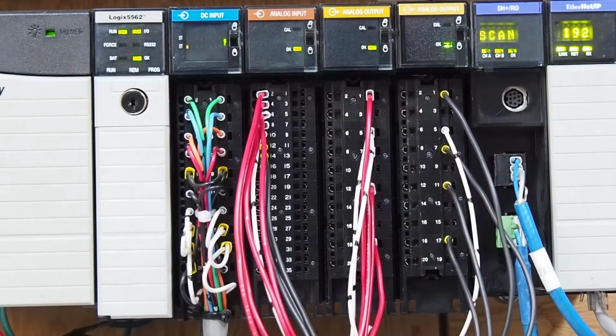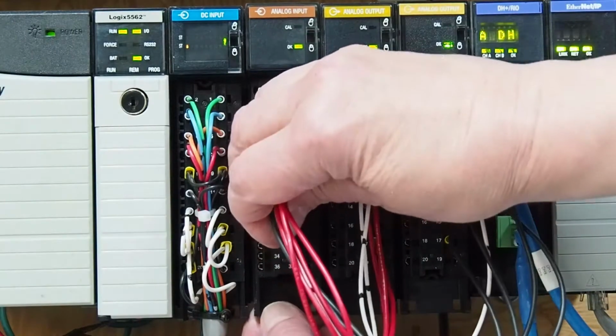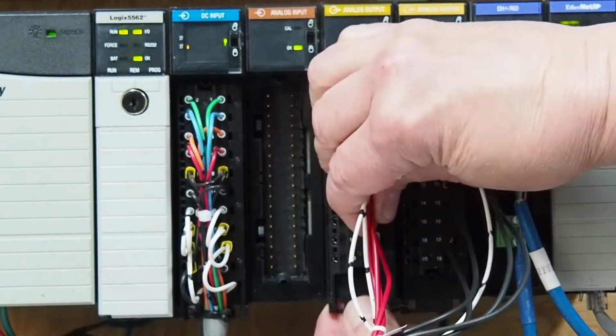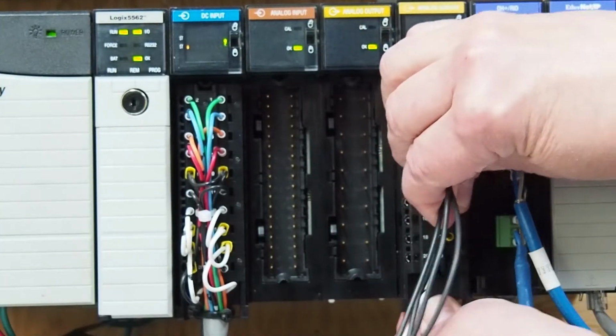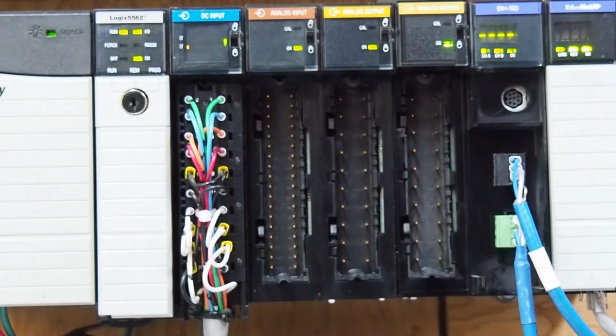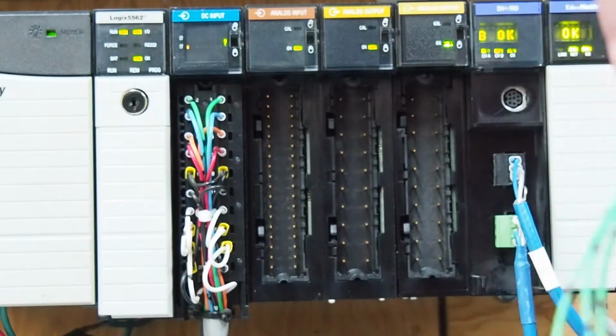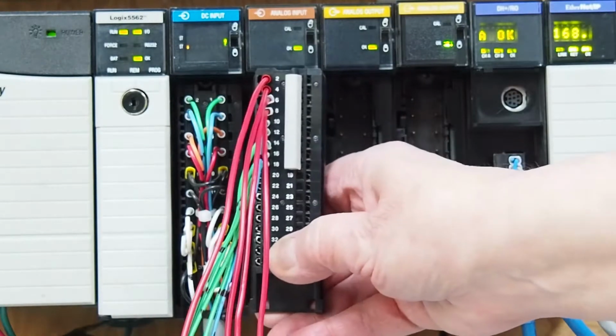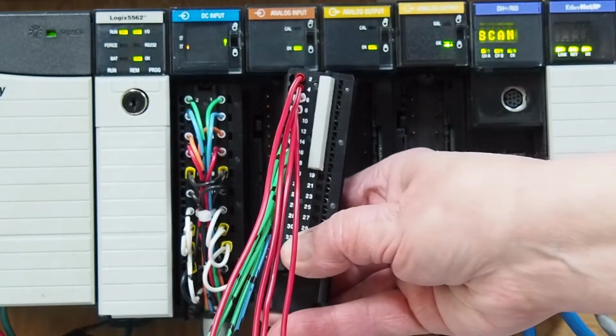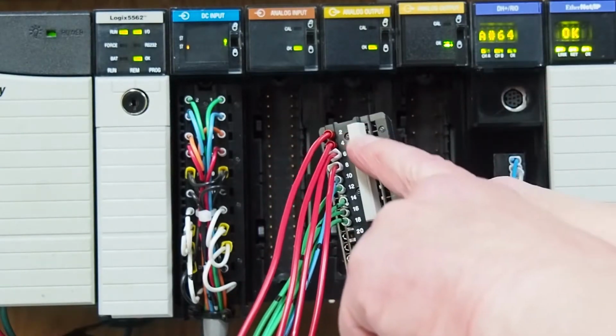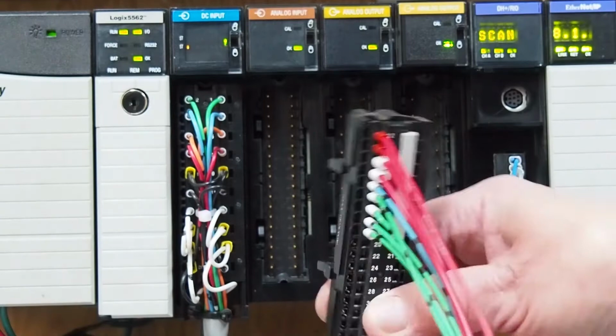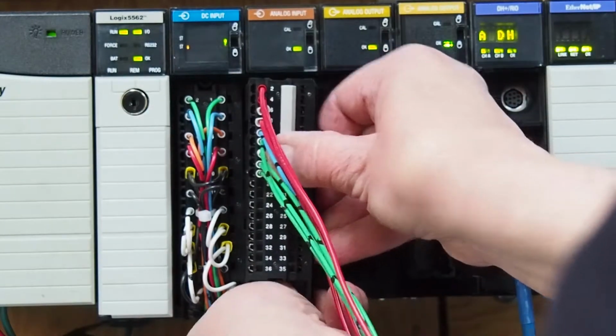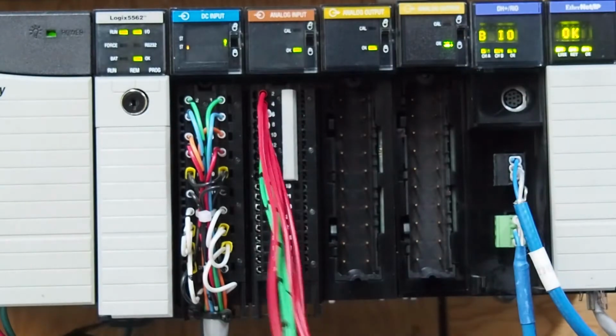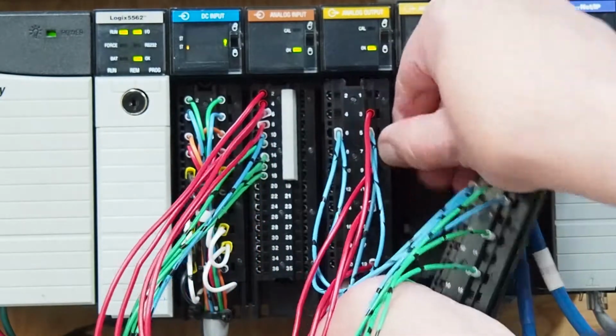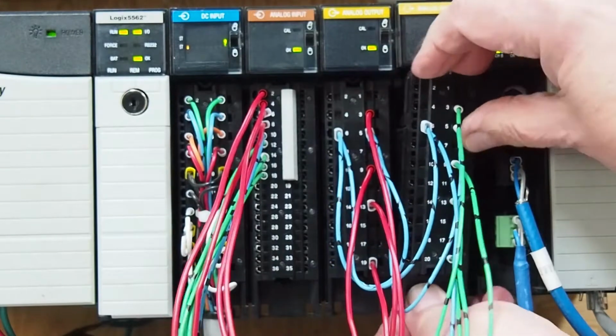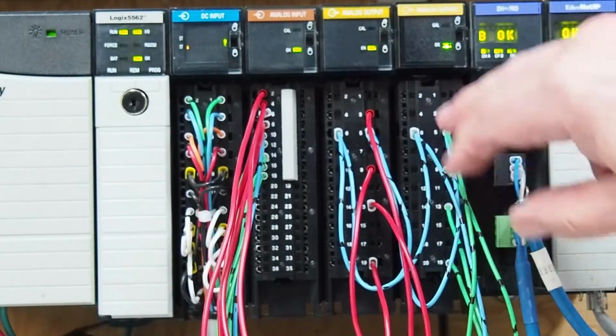So that's voltage mode. Now in milliamp or current mode, we just take these off, and I have another set here. This is for current mode, single-ended, and what it does is these 9 pins here are all jumpered together with a single bar. And on the outputs, all of the returns are jumpered together.